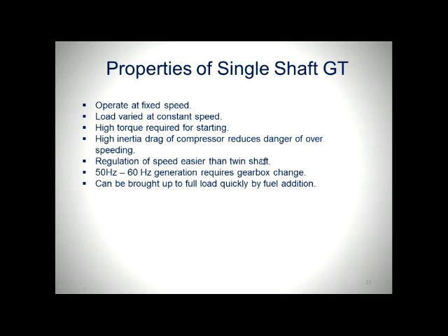Regulation of speed is easier than a twin shaft, and this is quite easy. Well, if you change from 50 to 60 hertz generation, you require to change the gearbox because they run at constant speed. But they can be brought up to full load really quickly because all you've got to do is put in more fuel, so it's not really a problem.